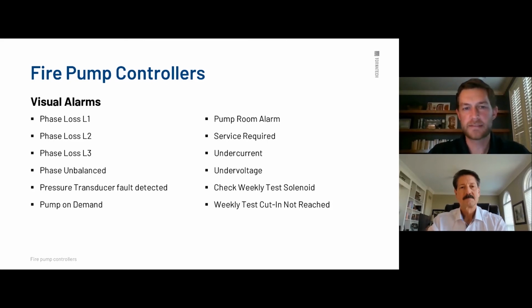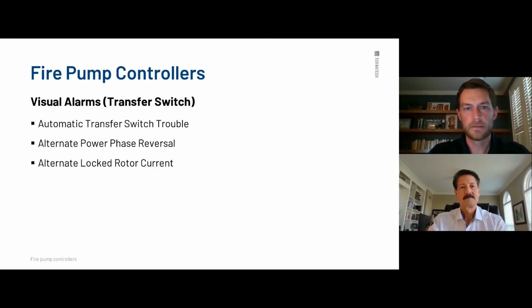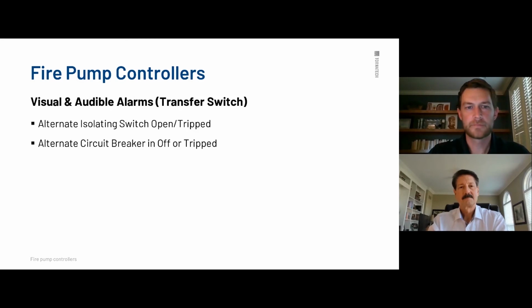These are more of the visual alarms. Phase loss, like I mentioned, is definitely a critical alarm. Phase unbalanced, pressure transducer fault detected. There is a lot of different things that we're having to keep track of constantly. More visual alarms on the transfer switch: automatic transfer switch trouble, phase reversal, locked rotor current. And some of the audible ones, like I mentioned before, if the transfer switch is open or it's tripped, it's not functioning, that's actually going to be ringing the bell. So that one is a critical one. The critical alarms are going to get a bell ring as well as a visual indication.